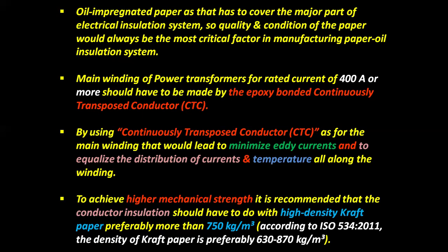To achieve higher mechanical strength, it is recommended that the conductor insulation be made with high density kraft paper, preferably more than 750 kg per cubic meter. According to ISO 534:2011, the density of kraft paper is preferably between 630 and 870 kg per cubic meter.